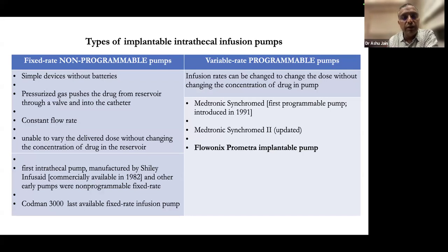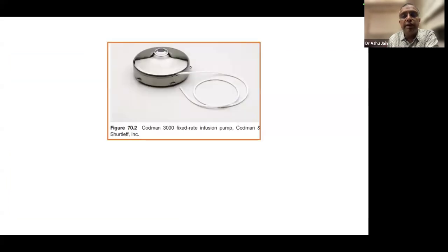But I have done these non-programmable pumps earlier with very good results. But now, unfortunately, we are finding it hard to get them in India. And the only pump currently available is this programmable pump from Medtronic. This is the pump where you can change the rate and the dose and everything by program, as you do for a spinal cord stimulator or these kinds of devices.